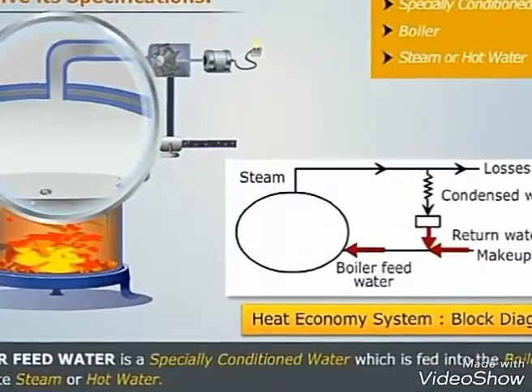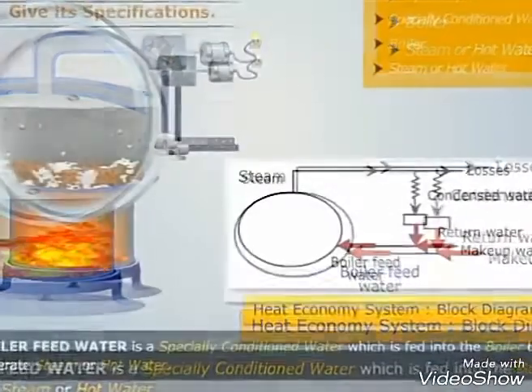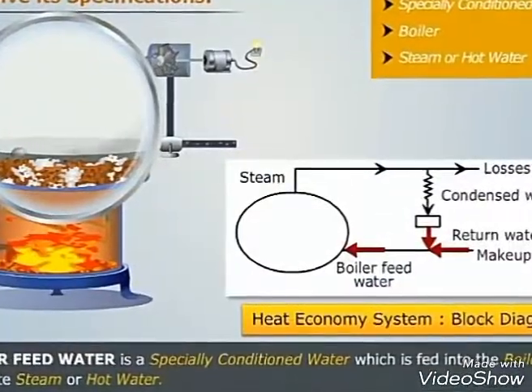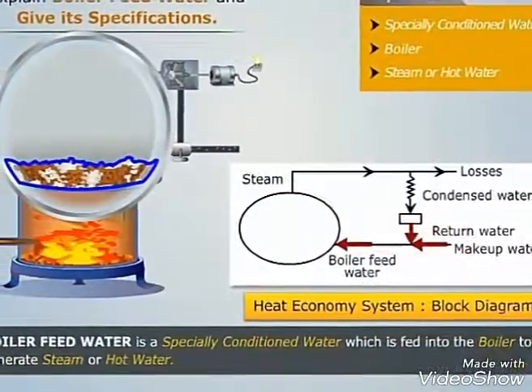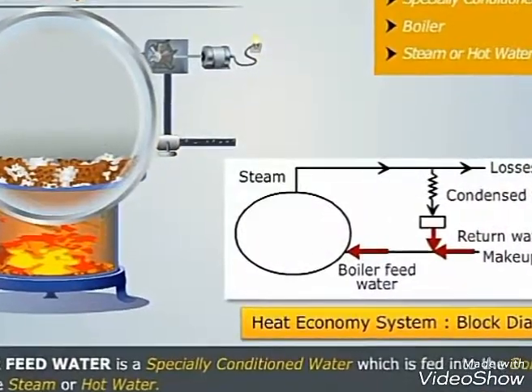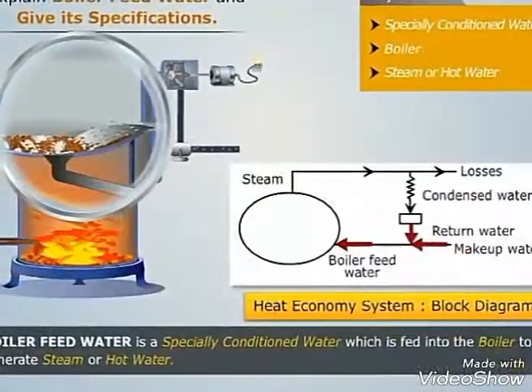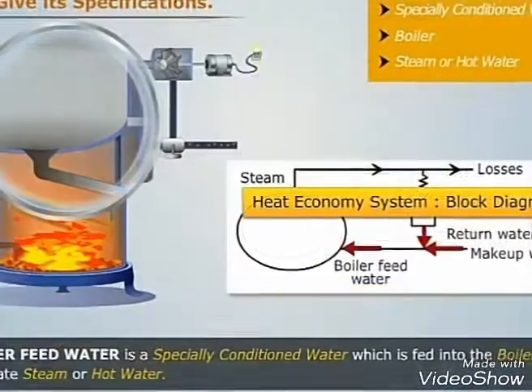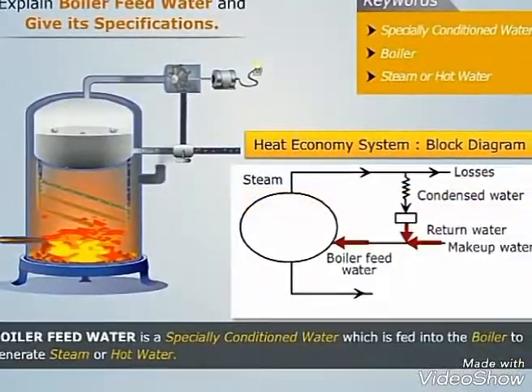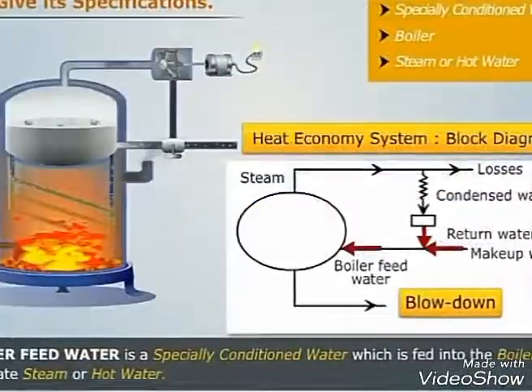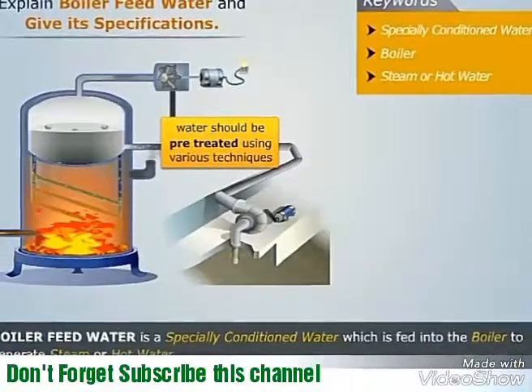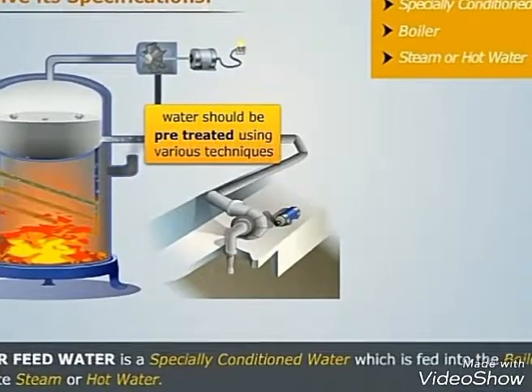Sometimes we see that some impurities settle down at the bottom of the boiler after the steam is produced. We know that steam which escapes from the boiler normally contains liquid droplets and gases. So the remaining water at the bottom of the boiler might pick up all the foreign matter from the water that was converted to steam. This results in the accumulation of impurities at the bottom of the boiler. These impurities can be removed by discharging some water from the boiler to the drain. Such a process of blowing the impurities from the boiler to the drain is called the blow-down operation.